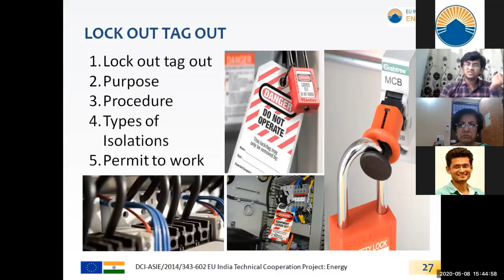The main purpose of lockout tagout is to isolate the energy sources. Whenever doing maintenance work, make sure you've switched off the electricity, done the lockout tagout, and confirmed there is no voltage in that section. If there is voltage, that means it's hazardous - there is trapped energy. You have to discharge the trapped energy and confirm there is no voltage before you can work on the electrical part. This is a key safety feature whenever doing maintenance.